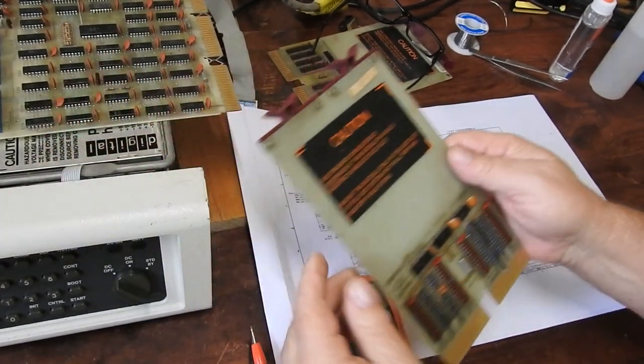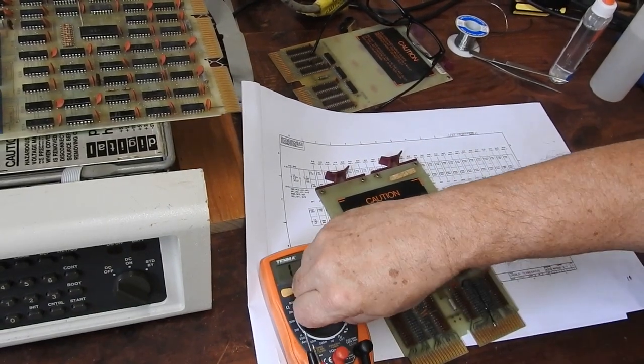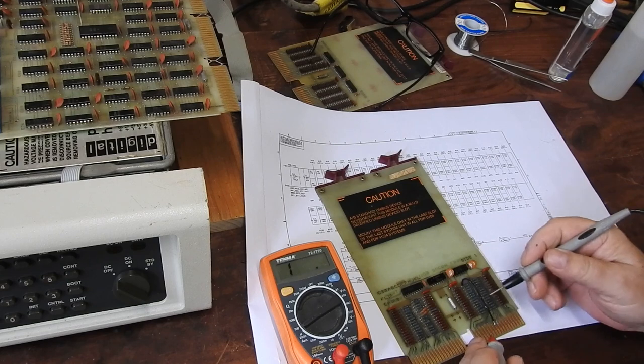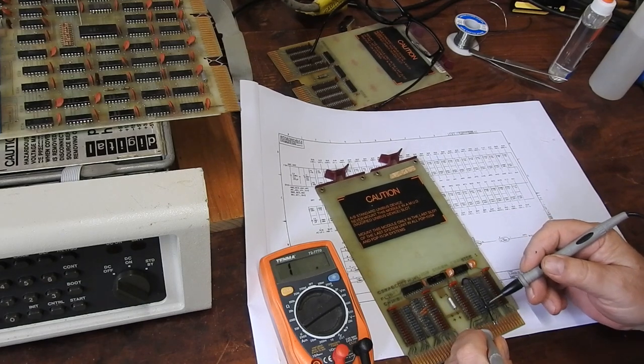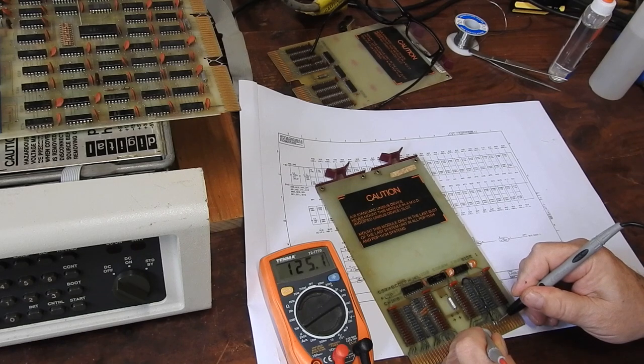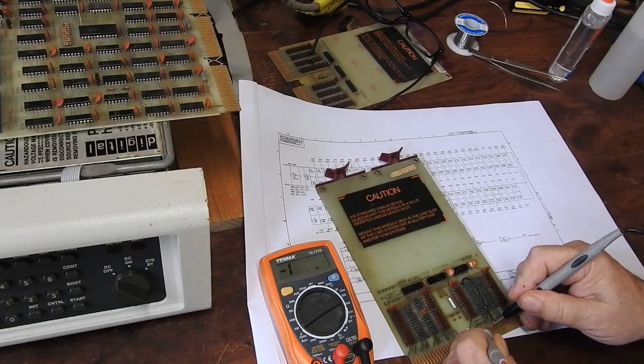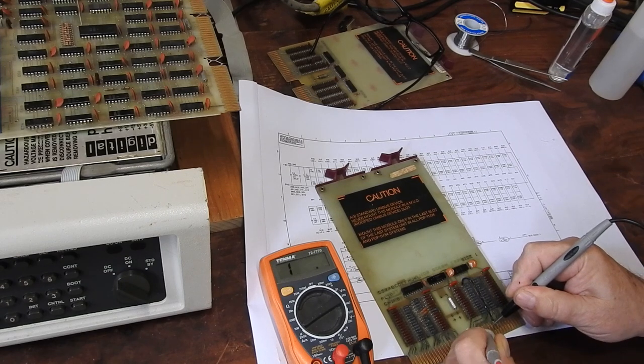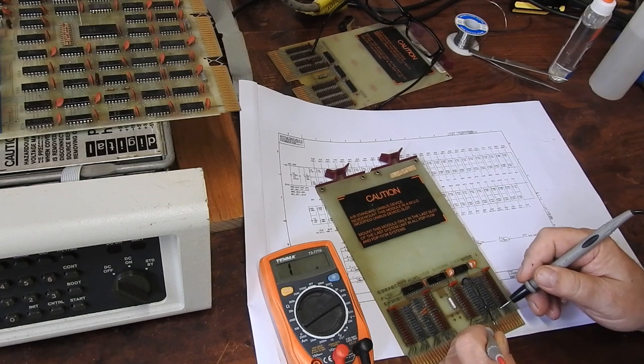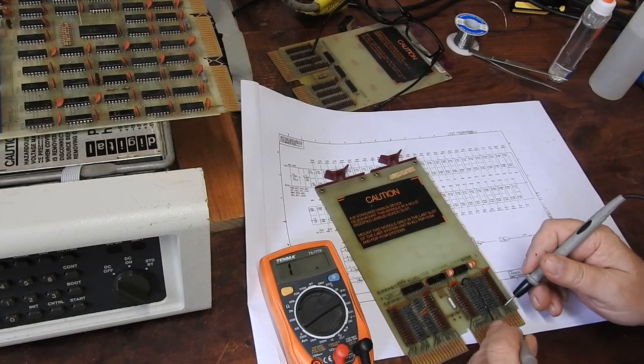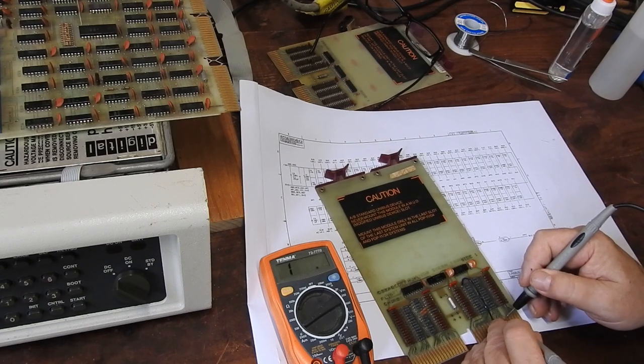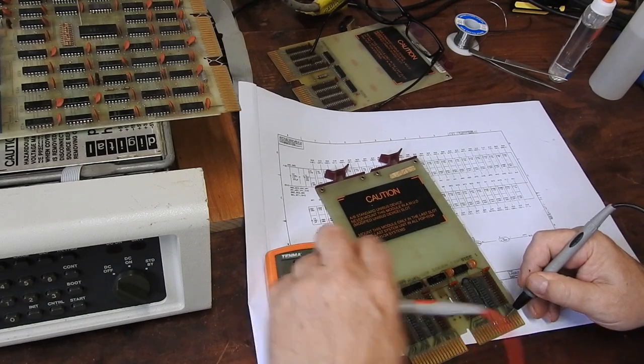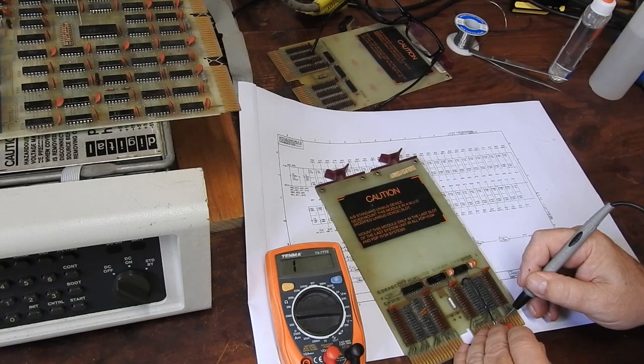And I've checked all the pins. Well, just checked, because I've got lacquer on there now, I have to use these ones here as a ground. Either side of that, we've got 123, the one that we fixed, 123, and one on the other side of it, 123-ish, yeah, 120-something. And as a double check for no cross shorts, if we look between any two of these terminations, we get 240 ohms.